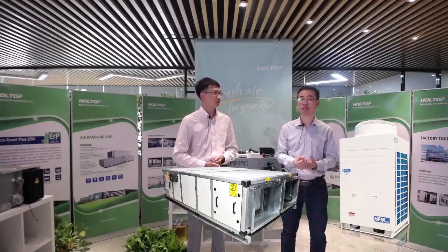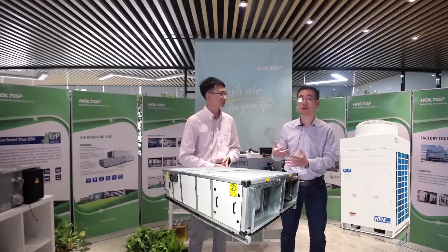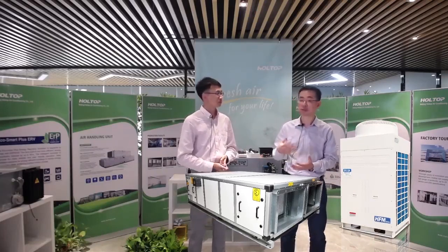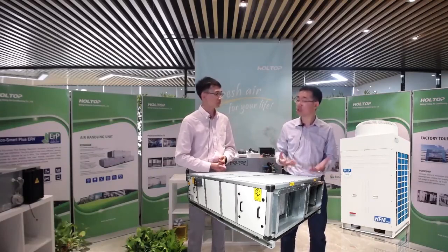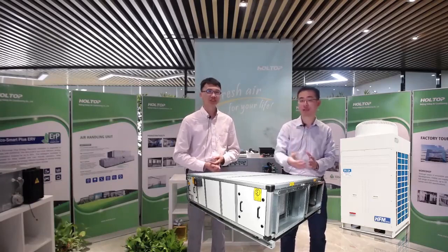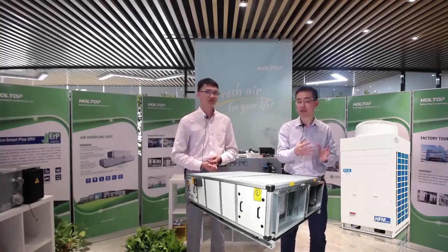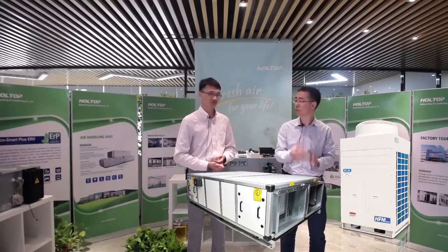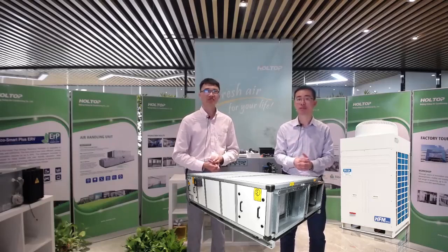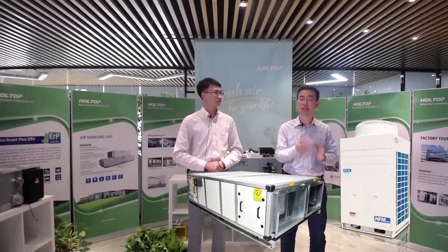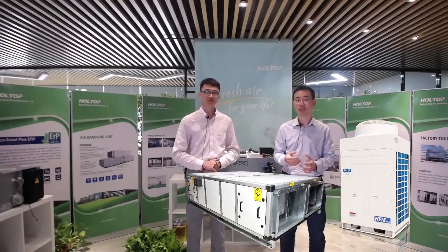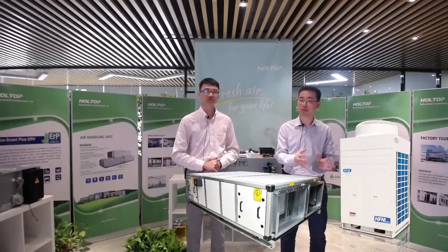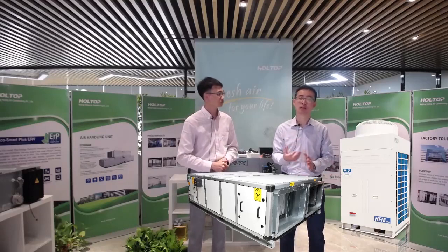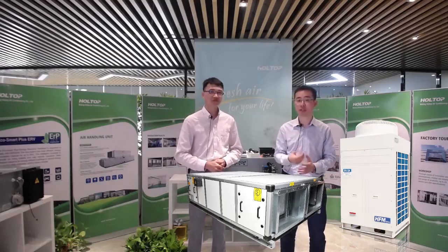This indoor circulation type is used for air conditioning to control the indoor air temperature. The key feature of this unit is the air on coil temperature is DB 27 degrees and WB 19.5 centigrade, and off coil temperature will be 16 to 17. For this temperature, as you see, it can be a very good solution for indoor air temperature control.